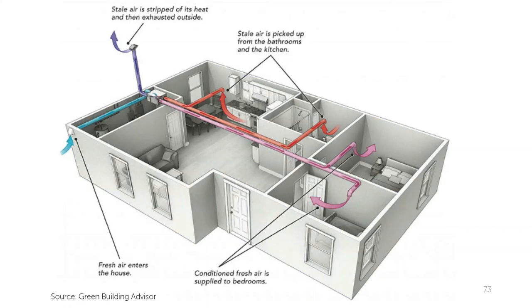Once you've established how much ventilation airflow you need, it's time to design a system that can deliver that ventilation efficiently and effectively to the occupants. Good system design considers where the polluted air needs to come from. In addition to kitchens and baths, are there any hobby rooms or other potential source pollution zones in the home? Advanced ventilation systems exhaust and supply air to every room in the home.